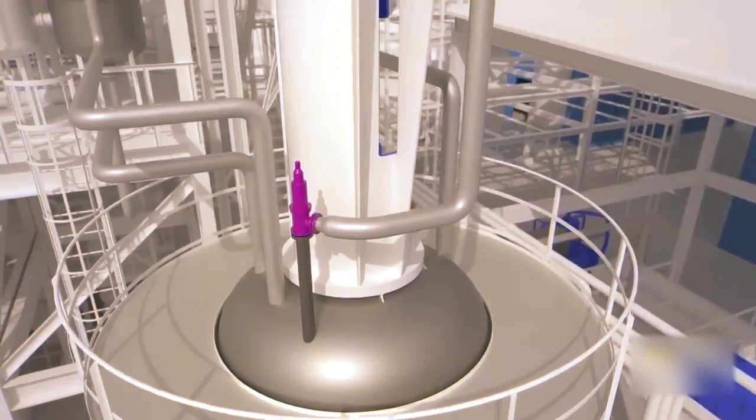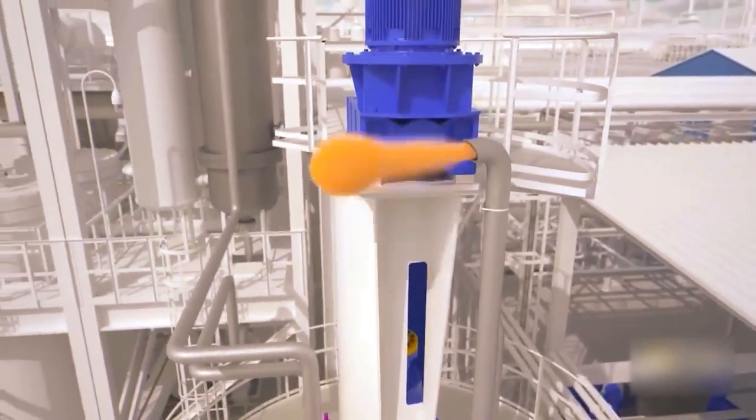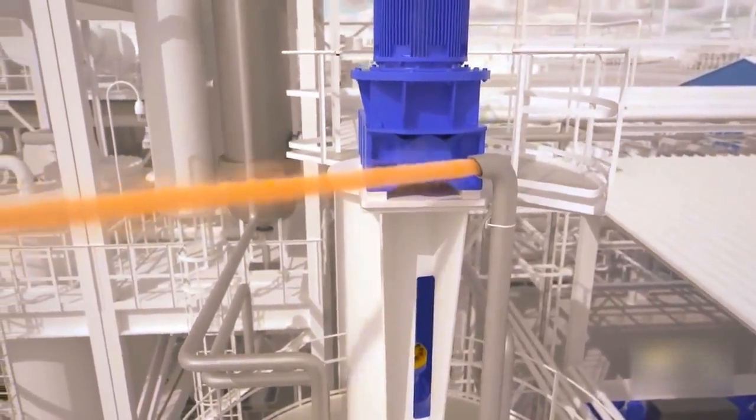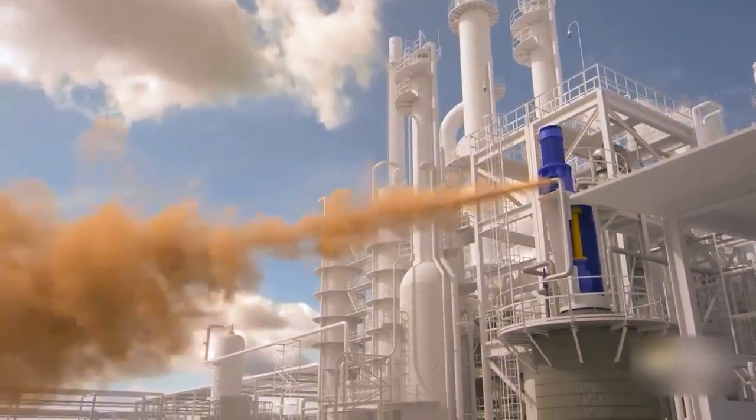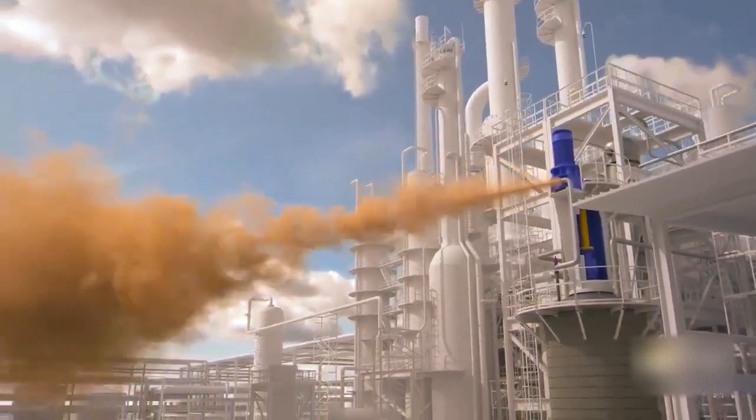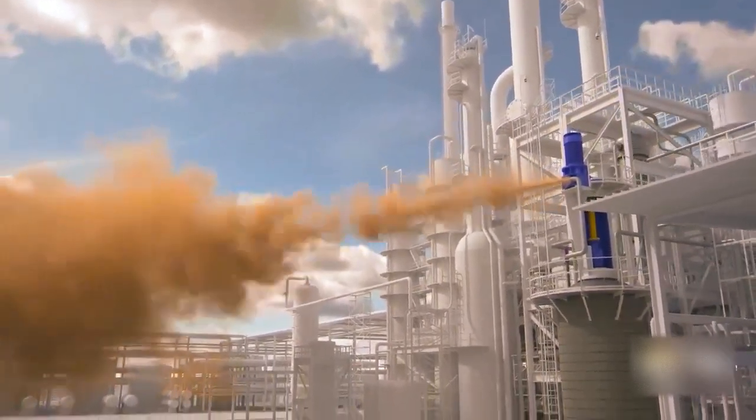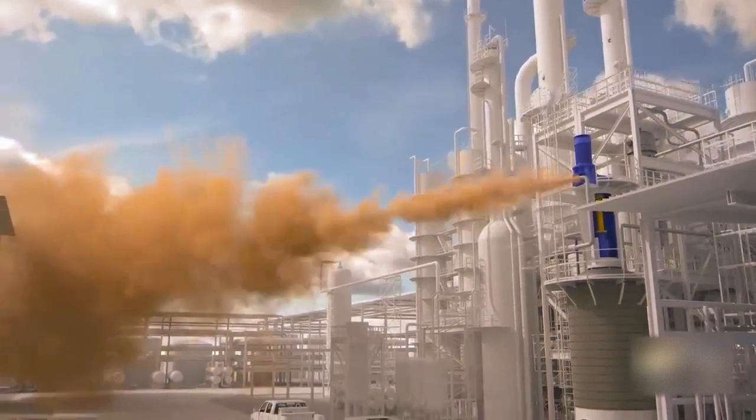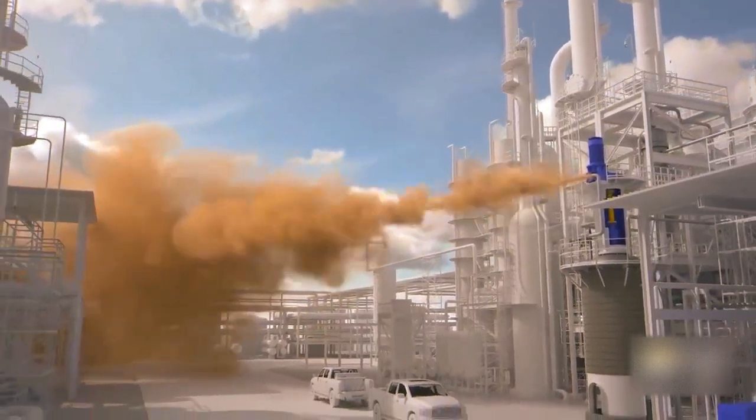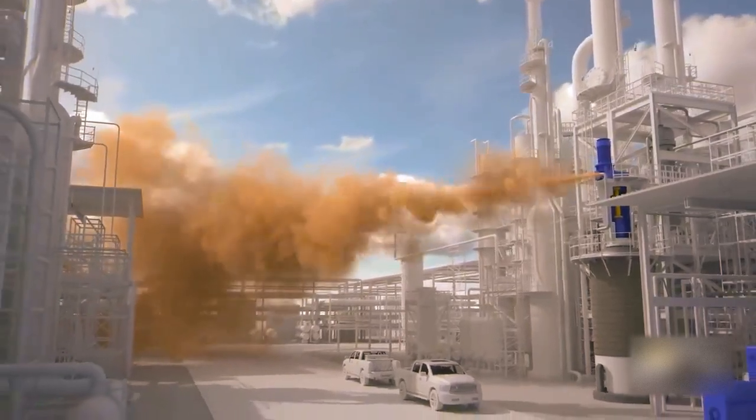Shortly before 10:30 a.m., the emergency pressure relief system activated. High-pressure ethylene vapor discharged from the reactor into the atmosphere. It was released horizontally toward an area where many people were working rather than vertically to a safe location.